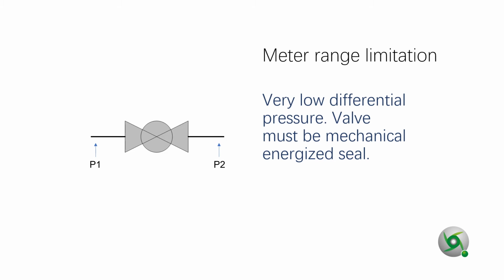There is normally very low differential pressure across the closed valve. It requires that the valve must be mechanically energized sealing. Sealing that relies on differential pressure will not work.